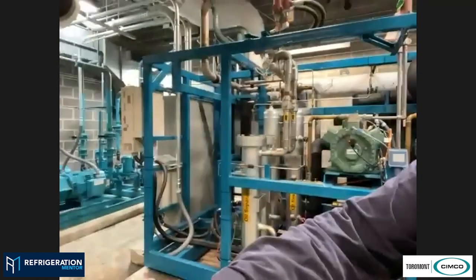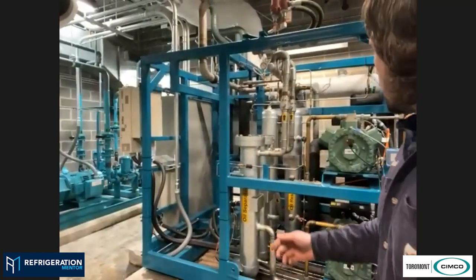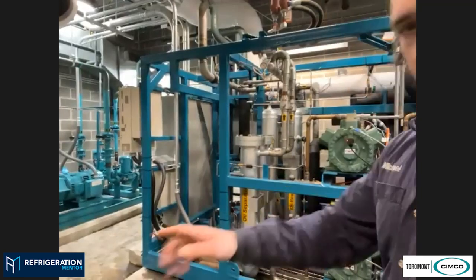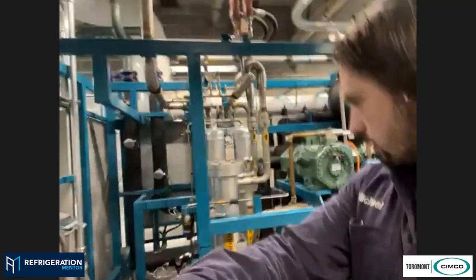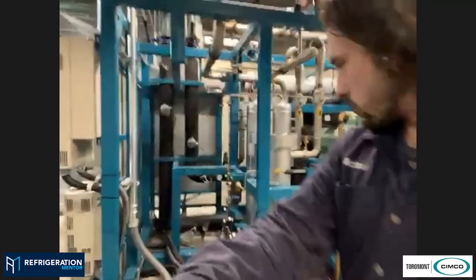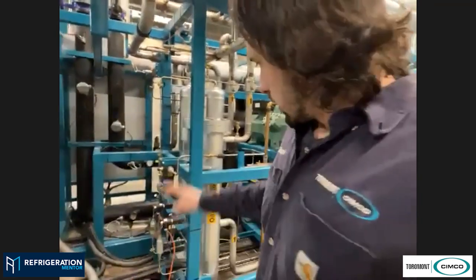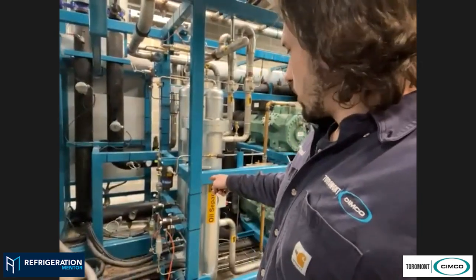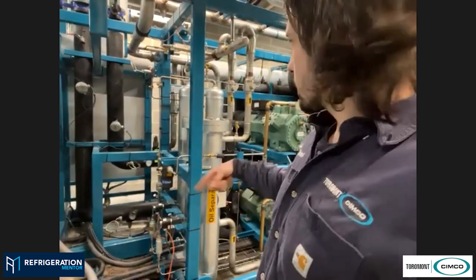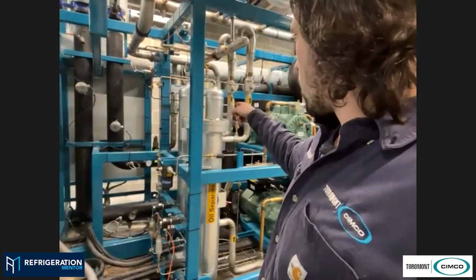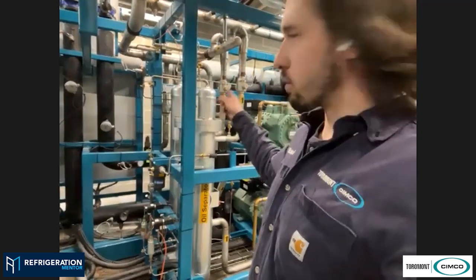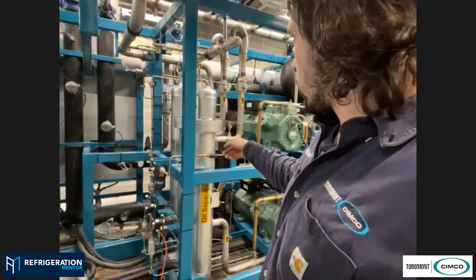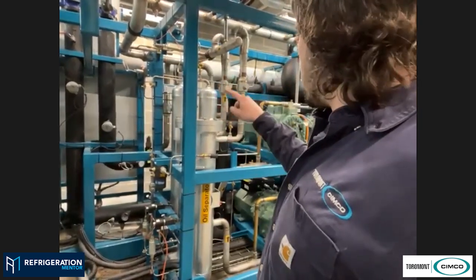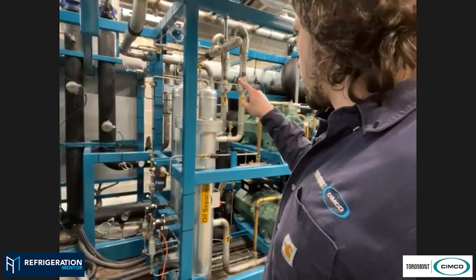We left off at the oil separator. For oil return, since we have two separate separators and two separate discharge headers, we have two oil return solenoids that cycle back and forth to return oil into our oil reservoir. The reservoir is at a lower pressure than our discharge, and we're running, by the book, a little over 100 differential between our reservoir and our compressor crank.